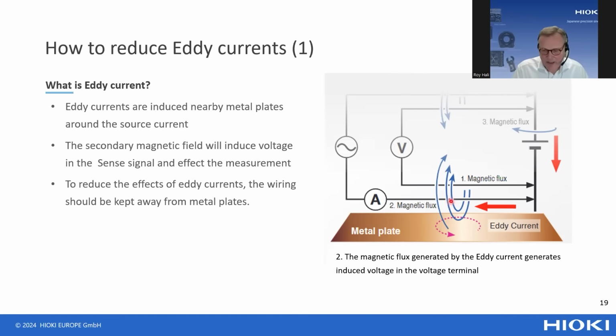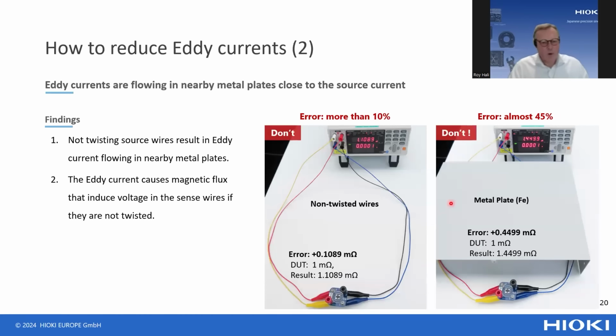To show the effect of eddy current, we repeated the first test without twisting the wires, and there's already a measurement error of 10%. But if we put a metal plate nearby the wires, the error increases a lot, to 45%, showing the eddy current has a very big impact.